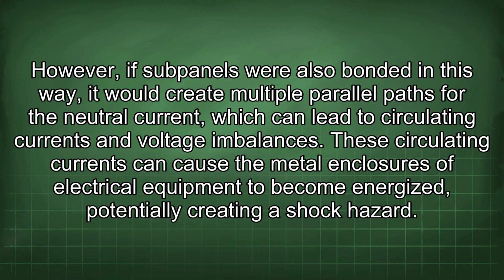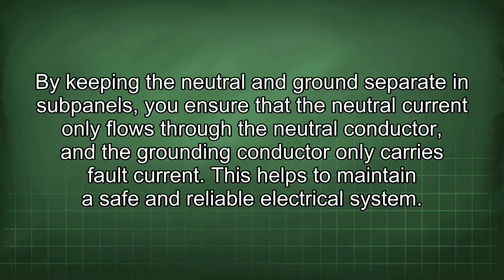However, if subpanels were also bonded in this way, it would create multiple parallel paths for the neutral current, which can lead to circulating currents and voltage imbalances. These circulating currents can cause the metal enclosures of electrical equipment to become energized, potentially creating a shock hazard. By keeping the neutral and ground separate in subpanels, you ensure that the neutral current only flows through the neutral conductor, and the grounding conductor only carries fault current.